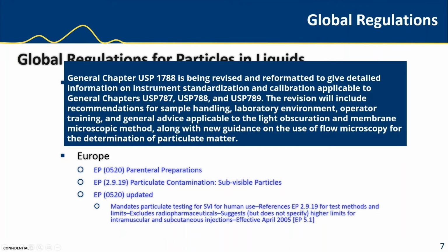So for particle counting and sizing tests, USP 788 recommends routine testing using microsphere test standards and background count check using either filtered drug product or water blanks. So we're seeing an increase in effectively what we've been doing every 6 months with USP 788 validation of the liquid particle counter. So that's really an important one to watch out for.